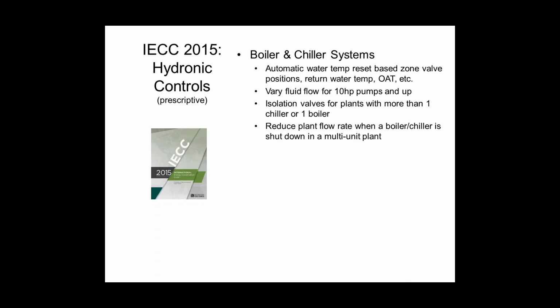Systems that have 10 horsepower pumps and above, you have to have variable flow, variable speed drives basically. So from the control side, plan on controlling those. As soon as you have 10 horsepower pumps and up, you should know in your bid, I need to have a VFD in there, or somebody does, and I've got to control the VFD.